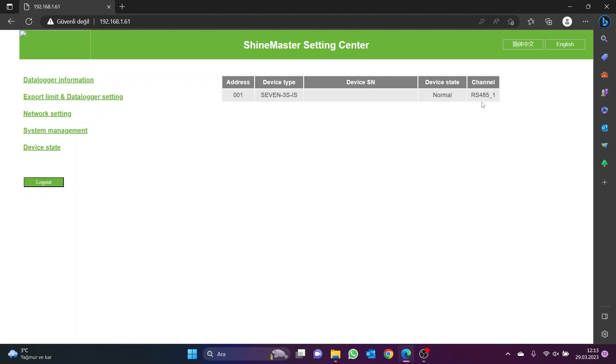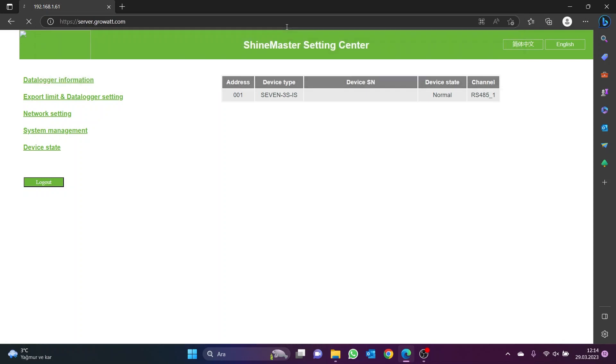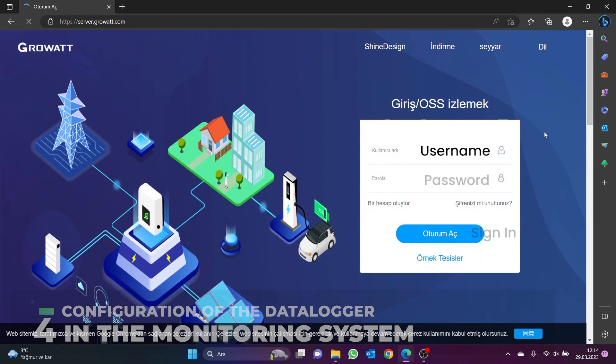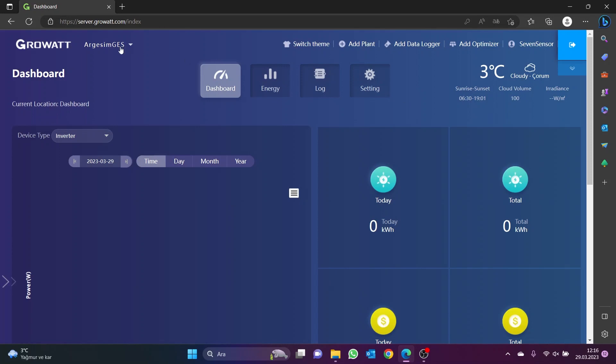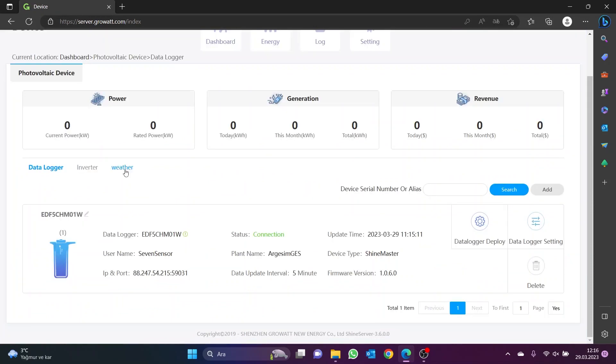Once the sensor configuration has been successfully completed in the Data Logger configuration interface, the ShineServer monitoring system is accessed. To access the ShineServer interface, log in to server.growatt.com from the browser. On the monitoring system page that opens, enter the username and password and click the Sign In button. After logging into the monitoring system, the PV project to be supervised is selected on the dashboard screen. Then go to the All Device page and open the Data Logger section to add the SevenSensor to the ShineServer monitoring system.